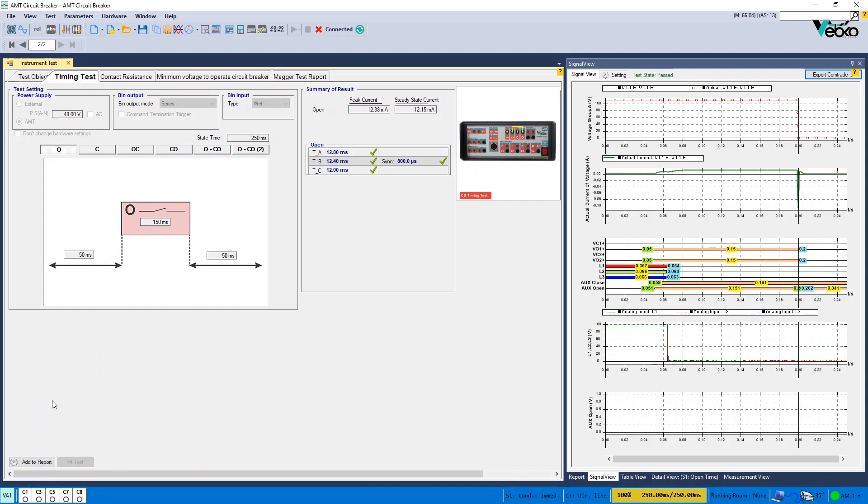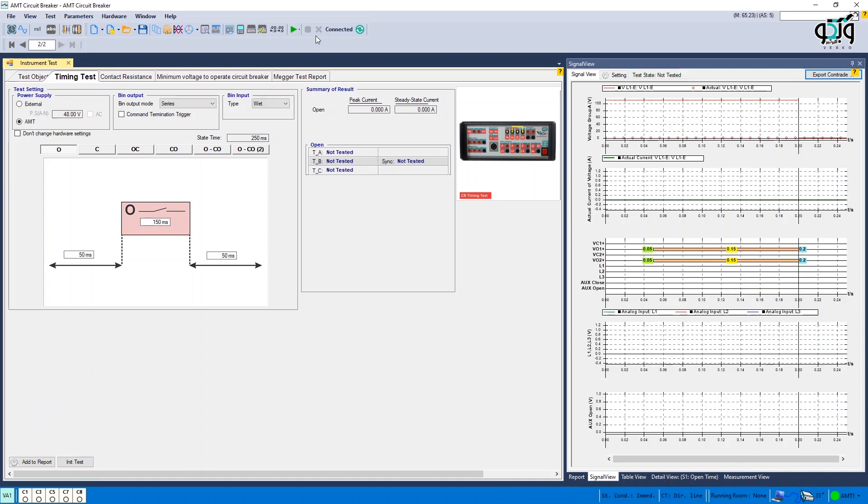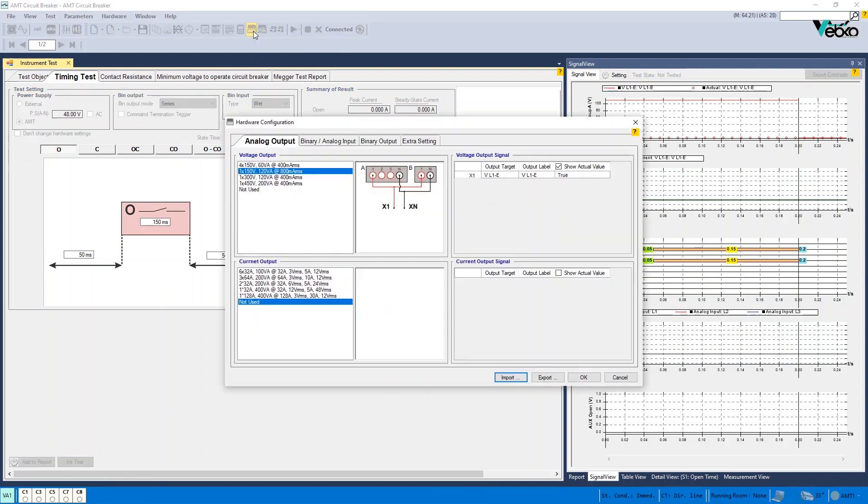In the following, some points about the test are provided. The first point is that if you wish to use only one voltage group, if you need to press Init Test and then check Don't Change Hardware Setting and by going to the Hardware Configuration, activate your intended voltage phases and deactivate the others in the Analog Output tab and perform the test using only the voltages of the intended group.